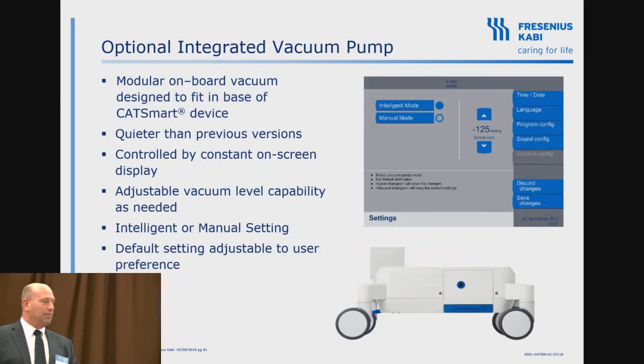We do have an optional integrated vacuum pump source in the base of the unit. It's down there at the bottom, a little blue dot. When we first came out, we had the intelligent vacuum suction, which means it has to sense resistance and then it'll ramp up and get to that set level. A lot of surgeons don't like that second or delay. So we now have a manual setting that's set right at whatever you want, and it can stay there. We also have a default setting where you can set, when you turn it on, it'll set at 100 or 150, 200, whatever. Our range is only 100 to 300. I've seen ORs, as you all know, where wall suction can be 600, 700. 300 is the highest we go.